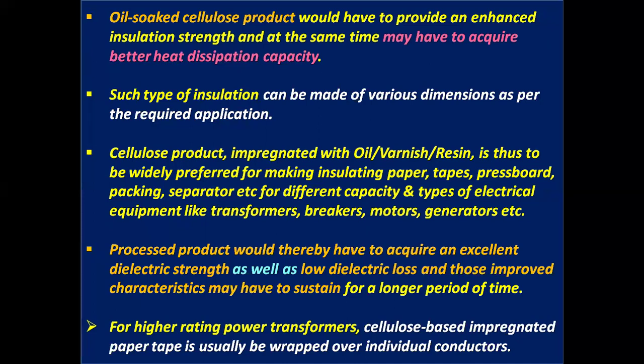Such type of insulation can be made of various dimensions as per the required application. Cellulose product impregnated with oil or varnish or resin is widely preferred for making insulating paper, tapes, pressboard, packing, separator, etc. for different capacity and types of electrical equipment like transformers, breakers, motors, generators, etc. The processed product acquires an excellent dielectric strength as well as low dielectric loss, and those improved characteristics may sustain for a longer period of time.